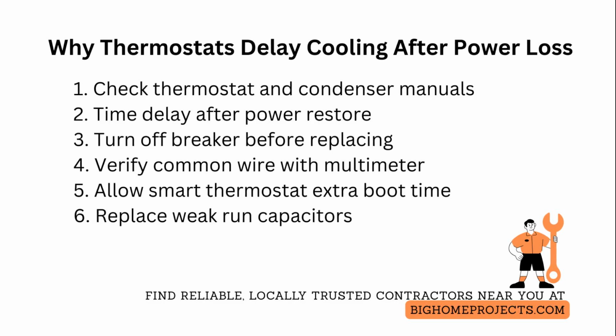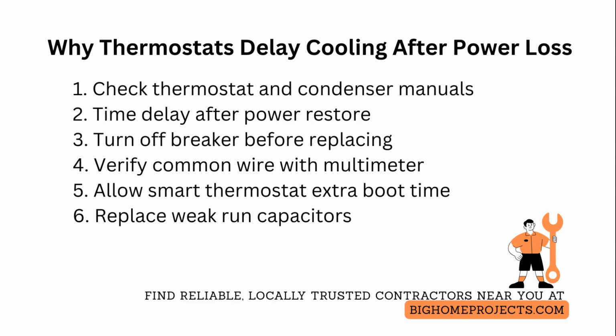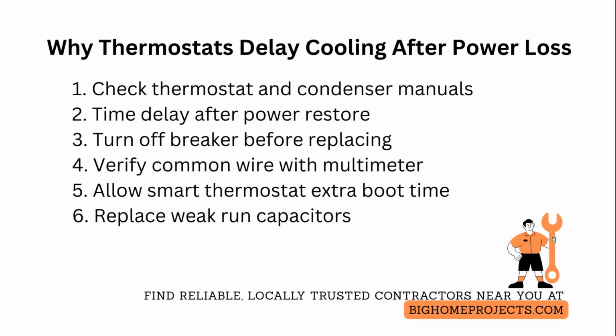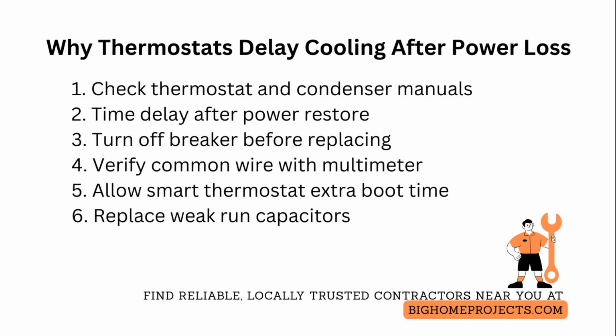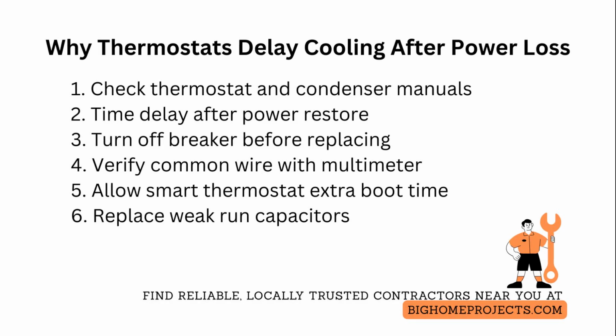For hardwired thermostat replacements, always turn off breaker power, verify common wire presence for continuous power, and use a multimeter to confirm 24 volts between the red and common terminals before swapping units to avoid triggering protective delays or boot-up sequences. When installing a new smart thermostat, allow for its own boot and network setup time, which can add 3 to 10 minutes beyond the compressor delay. If the thermostat shows a stable status light and still waits, the delay is at the condenser end.